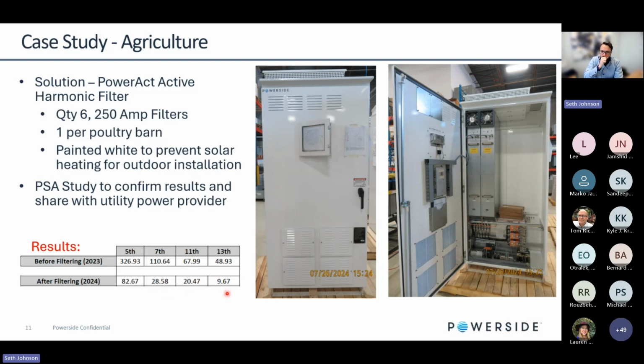So we were well within the spectrum, which brought the total harmonic distortion for voltage down below 5%, closer to 4%. Now we could further fine tune that and get that down lower if we wanted to add some more capacity to the system. But in this case, we're meeting and exceeding the utility power provider's requirements. And so this data was shared with the customer, which ultimately was shared back with the utility power provider, which turned out to be a great application for us.